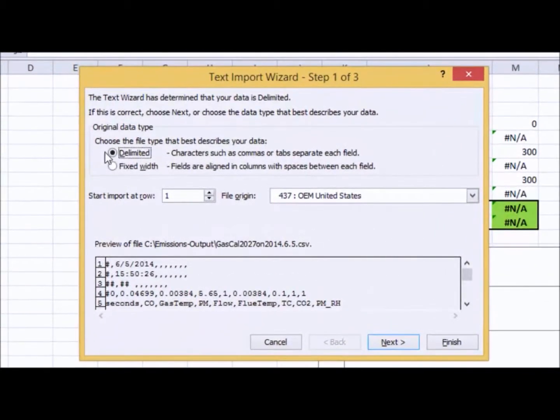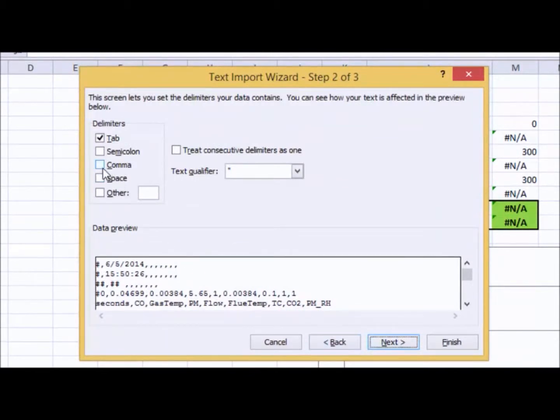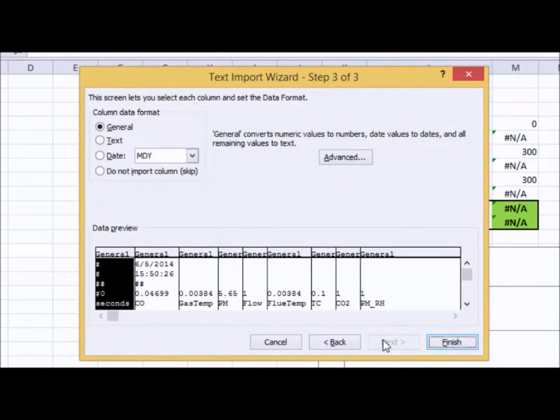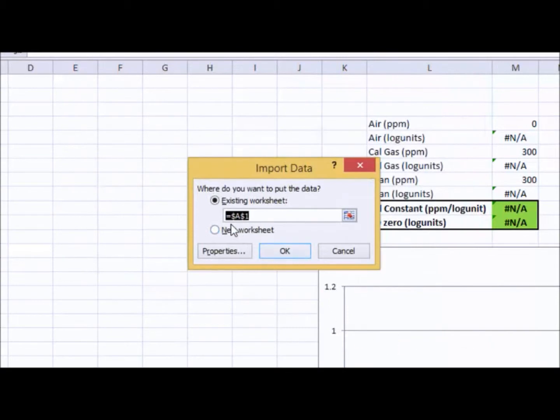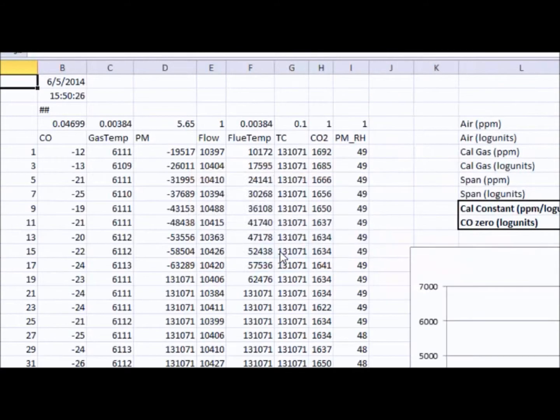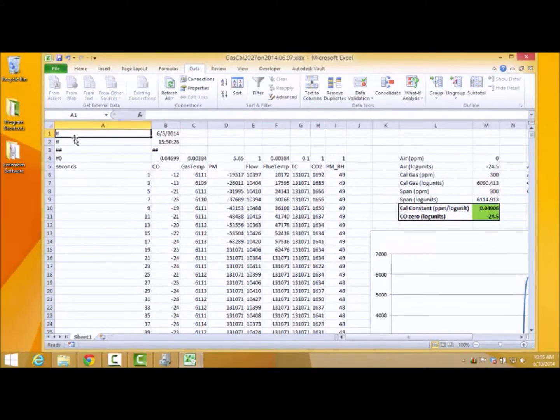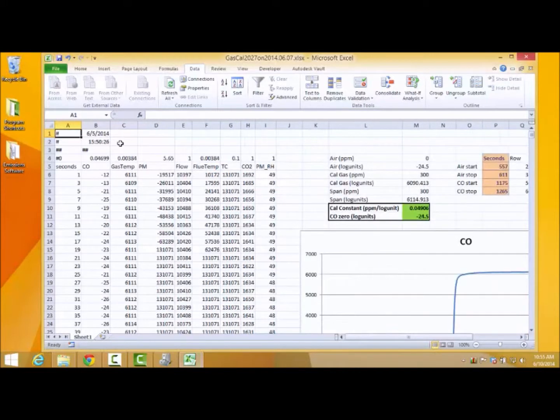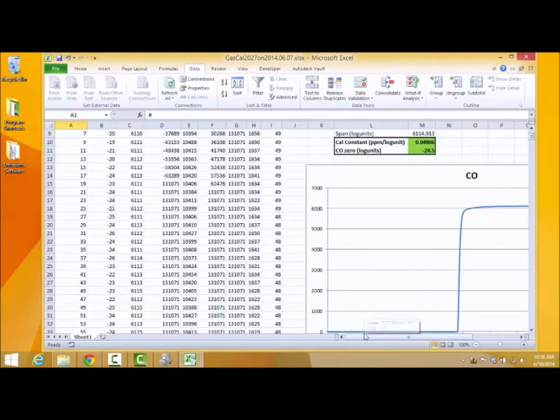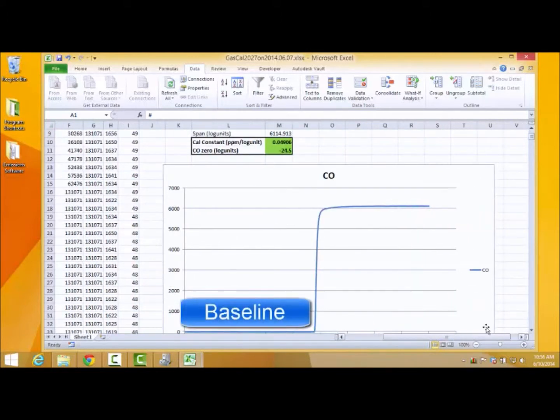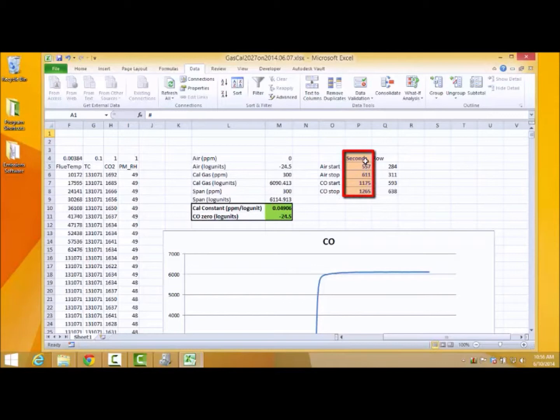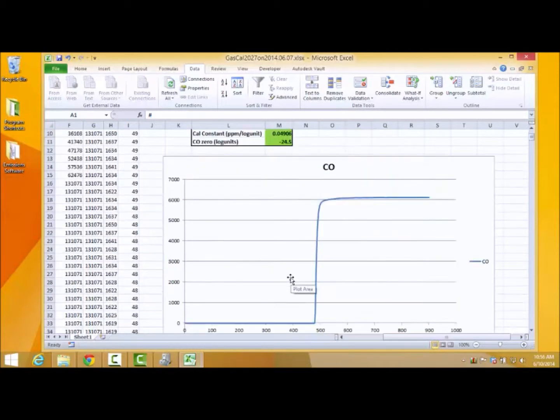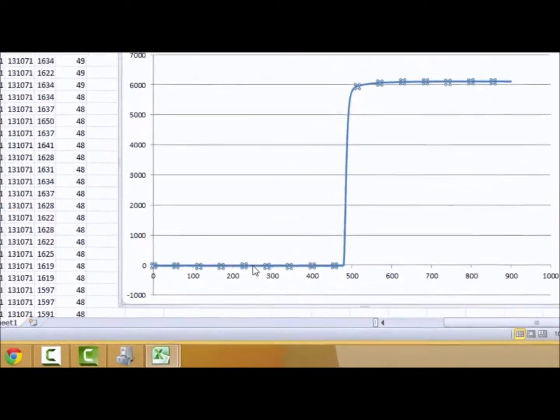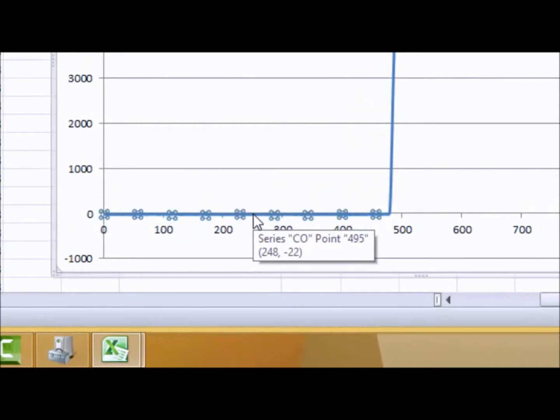Stepping through the menus, we know it's a delimited file. Make sure comma is selected, and keep the numbers in general format. Finish. Select cell A1 again, that should already be selected, and click OK. That should import all of your calibration data into the new worksheet. What we need to do is find an average of the baseline values and an average of the 300 parts per million values in the graph. We'll record those second numbers in this column here. To make it easy, you can hover your cursor over the lines and record the data points.